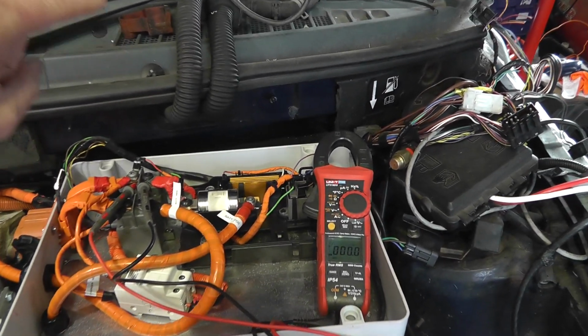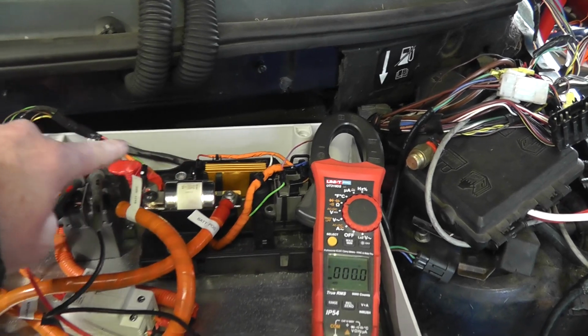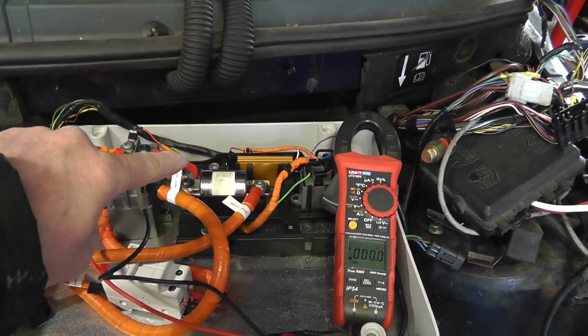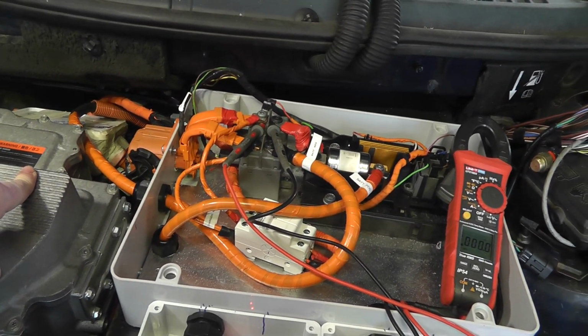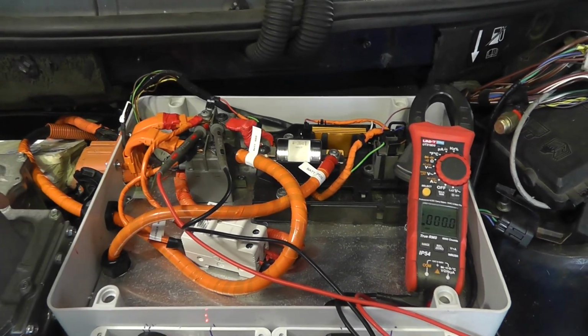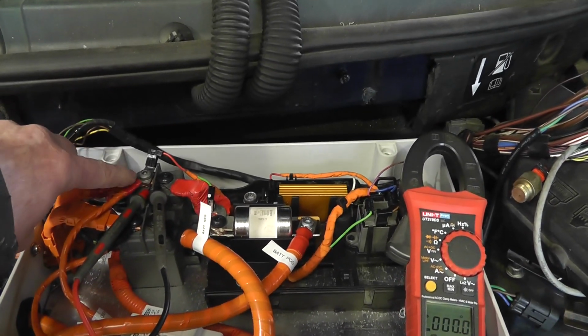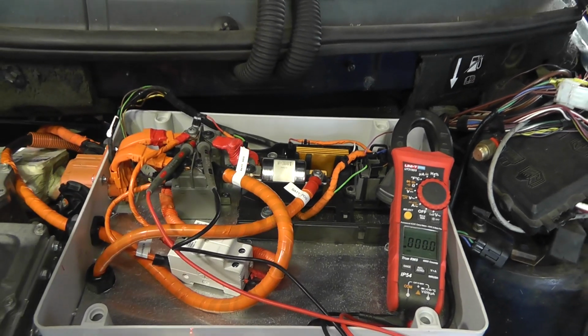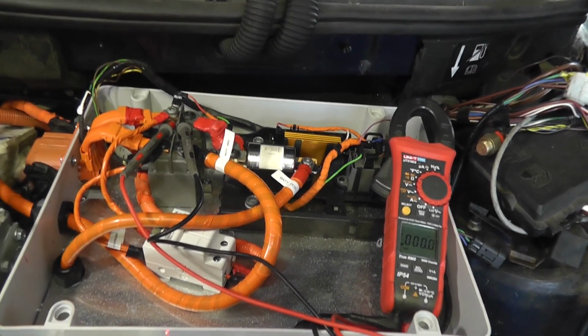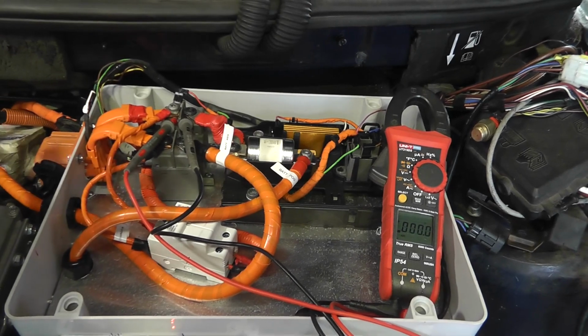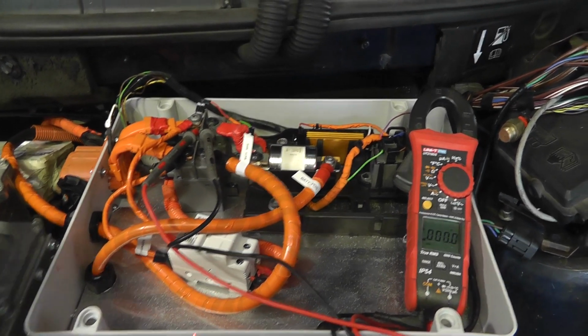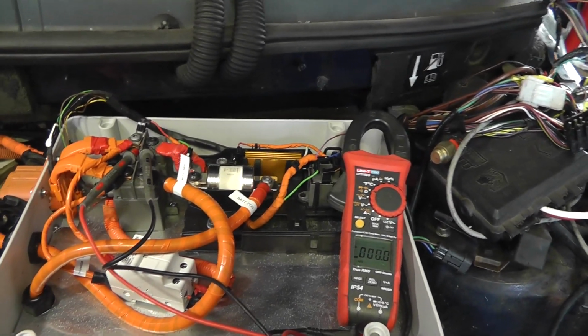So what you have to do first is gently feed the current in through a resistor, just until the capacitors get charged up. It only takes a second or two, and then you can flick on the main contactor, which gives you the main connection to the inverter, and at that point you can then remove the resistor.